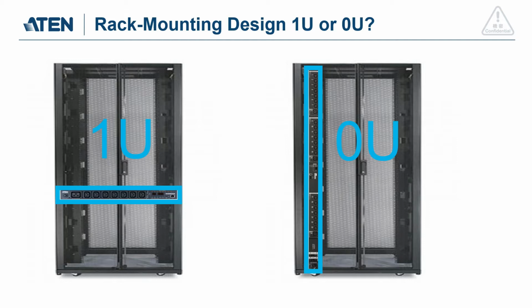We also have 42U long units, like the one on the right. These 42U units can actually be installed in a way that they don't occupy any of your rack units, which is why we call them 0U. Usually this 0U format comes in much higher density of ports, and if you want high amps, like 32 amps, you should go for the right one as well.